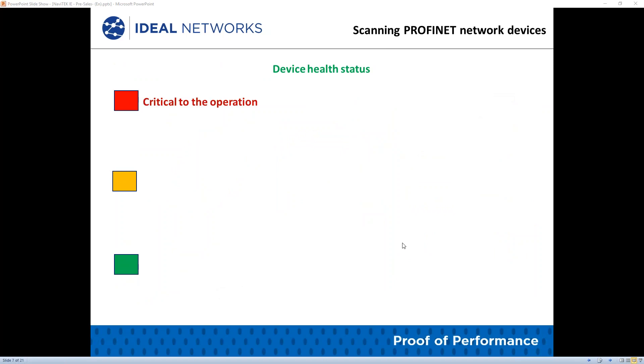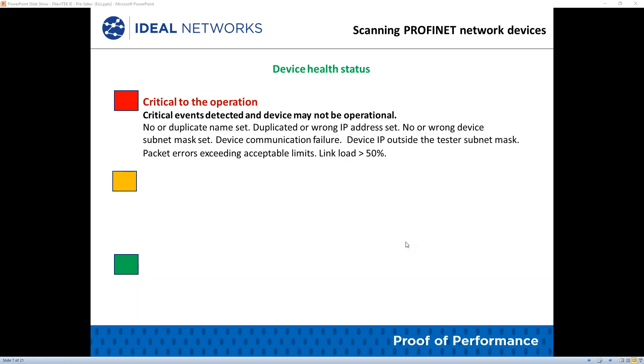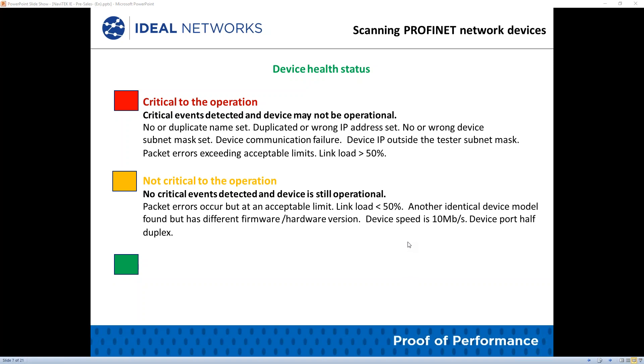Scanning the Profinet network devices uses auto detection and a device status indication of network health via a traffic light model. Red indicates critical to the operation — a critical event has been detected and the device may not be operational. Yellow indicates not critical to the operation — no critical event detected and the device is still operational. Green indicates operation is normal — no abnormal event is detected.